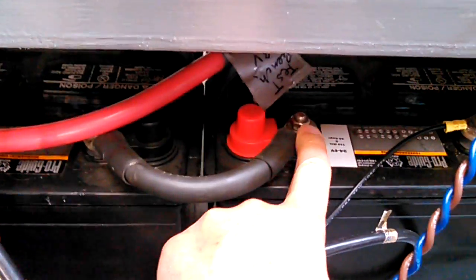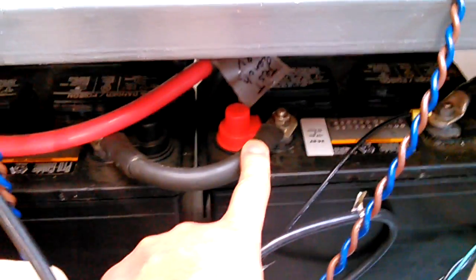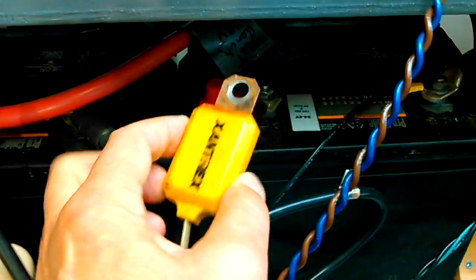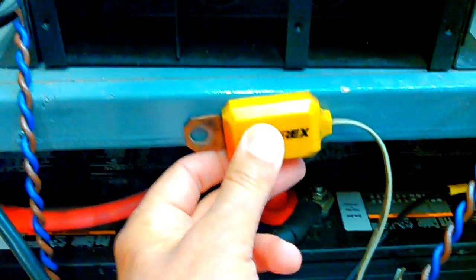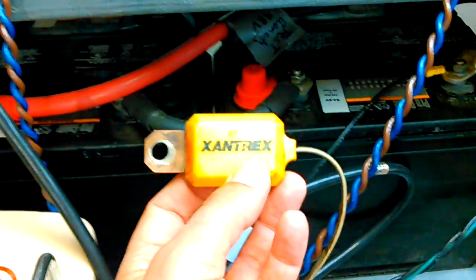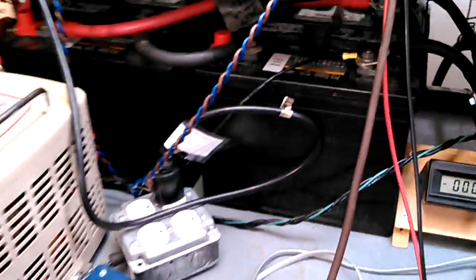If you continue to have problems with it giving you an over temp because of your terminals, one thing you've got to be sure of is that your terminal's in good shape. If you have a loose connection, a corroded connection, or a bad crimp, that could be causing the heat, and you need to look into that. But if everything is good, and you can't seem to find a spot that works well for you, these will work. Just put them in the vicinity where the batteries are. It's good enough. If it's 100 degrees outside, this temperature sensor will know that, and it will throttle back the charger so you don't boil your batteries. So that's the whole idea, and that's something to know about battery temperature sensors.